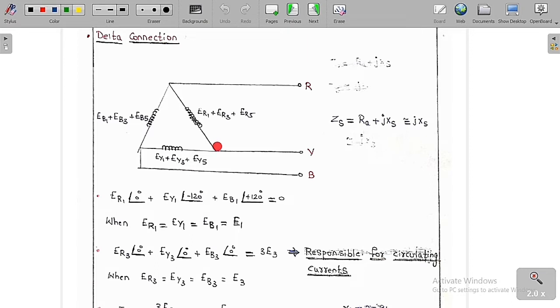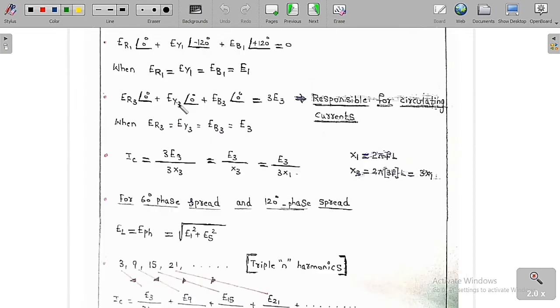Similarly, the fundamental component is the positive phase sequence and the fifth is the negative sequence. The summation of these two voltages never gives a resultant voltage - it is always equal to 0, so the currents because of these voltages are always 0. But ER3, EY3 and EB3 summation is not equal to 0, so they always produce some circulating currents. For the fifth harmonic analysis, ER5 at 0 degrees plus EY5 at plus 120 degrees plus EB5 at minus 120 degrees is always equal to 0. So the fundamental and fifth harmonic components never give a resultant voltage in the circular fashion, whereas only the third harmonic gives a resultant voltage, and because of that it is responsible for the circulating currents.